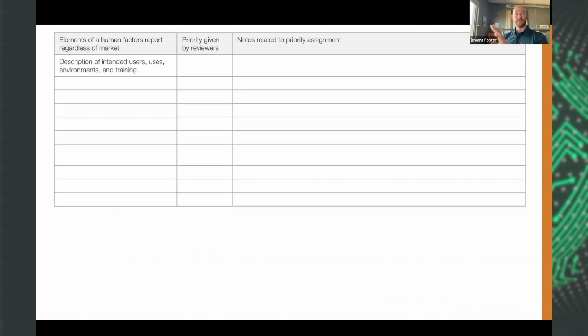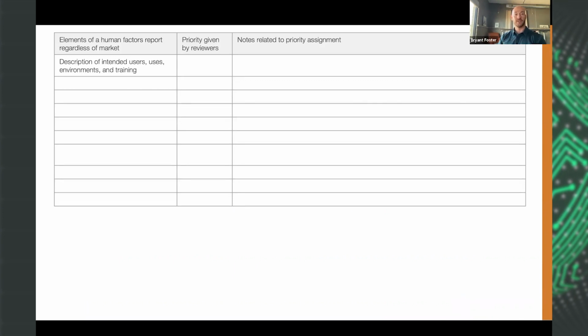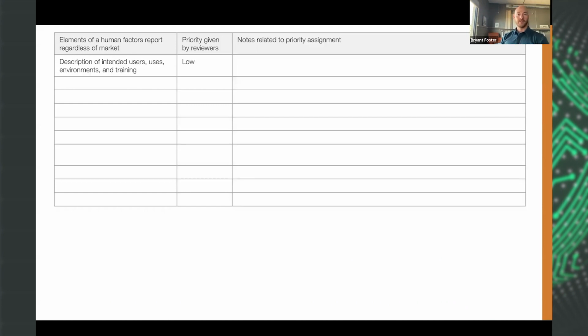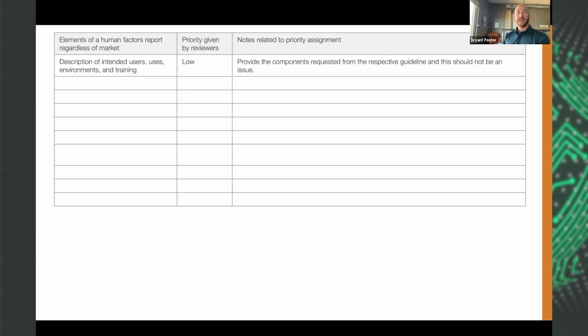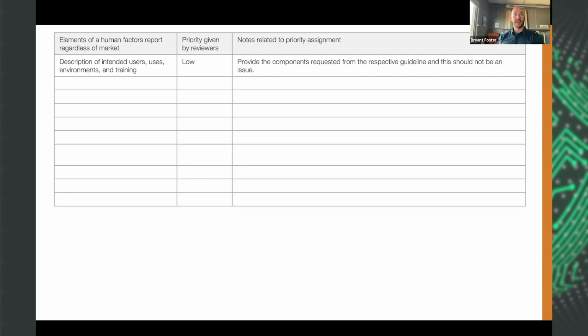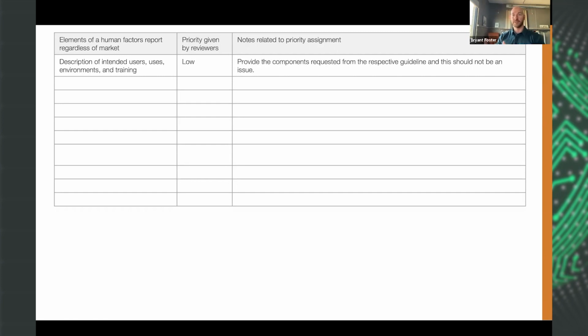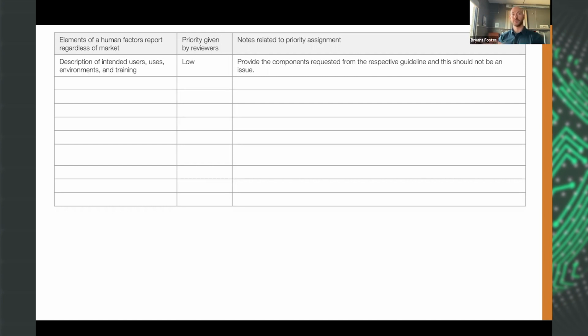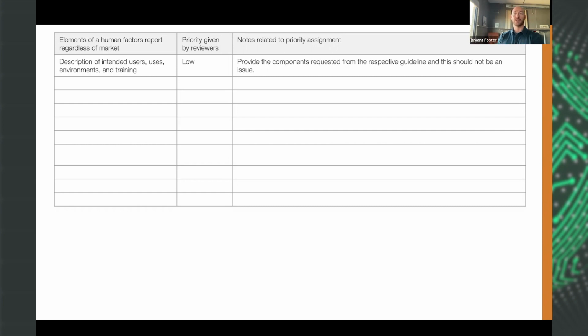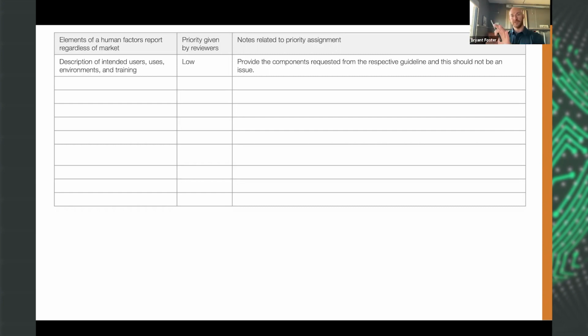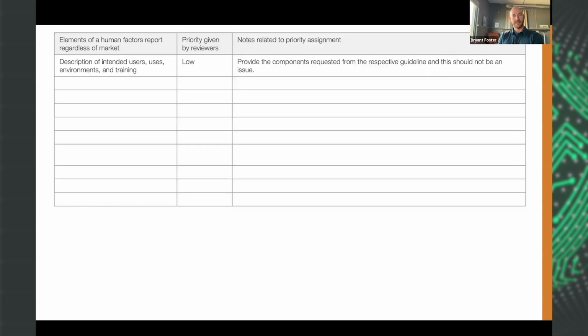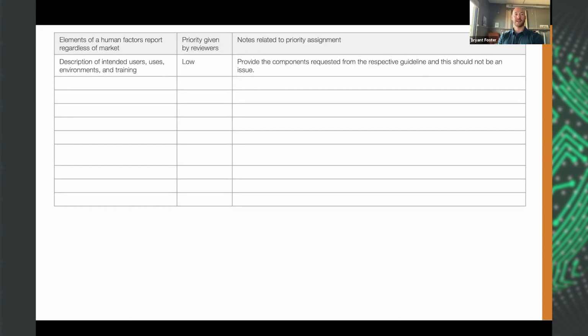The first is that every submission related to usability is going to need a description of the intended users, uses, environments, and training. That is a low priority given by reviewers, and I agree. Essentially, you just need to follow the guidance or guideline you're working with and provide that information. Again, those are the characteristics of who uses the product, identifying any potential differences that would cause them to be different user groups, and identifying the environments in which they use the product. If you stick with just providing what you need to identify, you're going to be fine there.